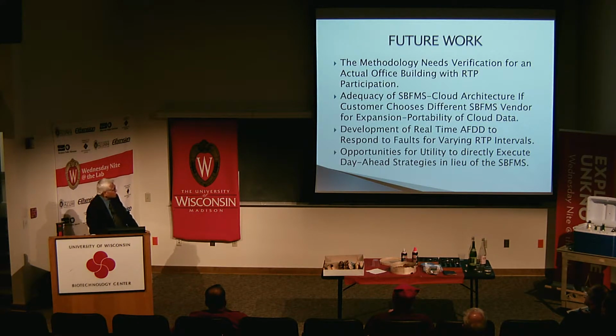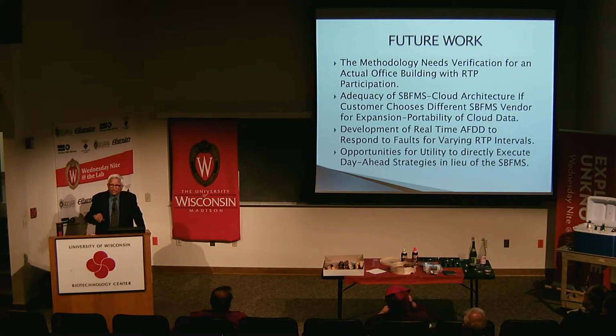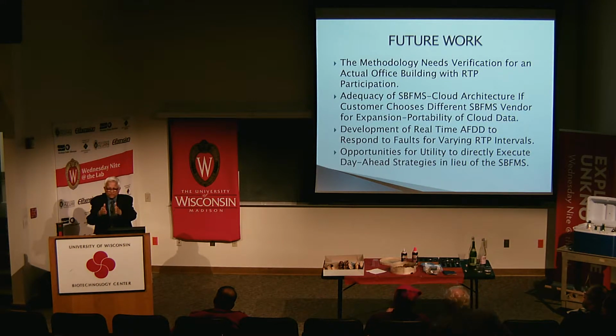Another interesting thing to do is the AFDD, which I will show in the next section. For demand response, the interval is so narrow that if a fault occurs, you may have to have dynamic AFDD, so that you constantly monitor it. You need a dynamic model and predictive control. As you move with time, the AFDD should move with time. Anytime it finds a fault, it should diagnose and restore the system. That needs further study. The last is for the utility to directly control the control strategies instead of the smart building facility management doing it.